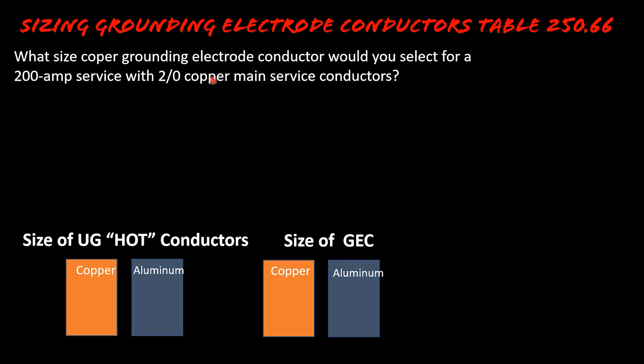So we head over to Table 250.66, read the black bold heading, make sure we're in the right table — grounding electrode conductor. We go to copper, find 2/0 AWG, come over to the copper grounding electrode conductor column, and we see that it needs to be a number four. No big deal, right? We learned about that yesterday. But here's where the breakdown happens.